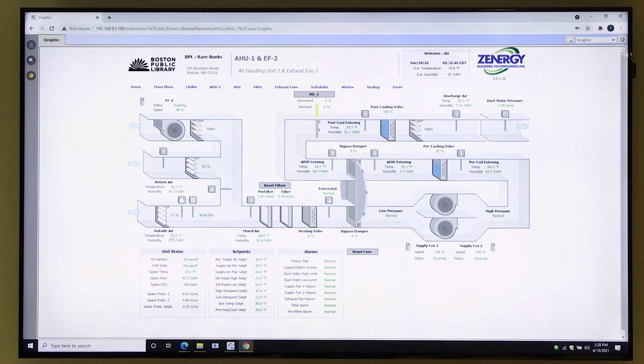There are other things down here that are important. Could you do it the other way? Could you reset it on the computer and then reset the drive, so that you can actually be there when it's starting? The problem with that is it's just going to go back into alarm. I'm just saying so that you can see if there's a problem. Could you run it in hand? You could. I think you might just have to have someone with you, because our main thing is in the basement and the fans are up in the roof. I see what you mean. I wouldn't want to hit reset and just hope for the best. No, I know. We need two people to do it. Which reset are you talking about now?